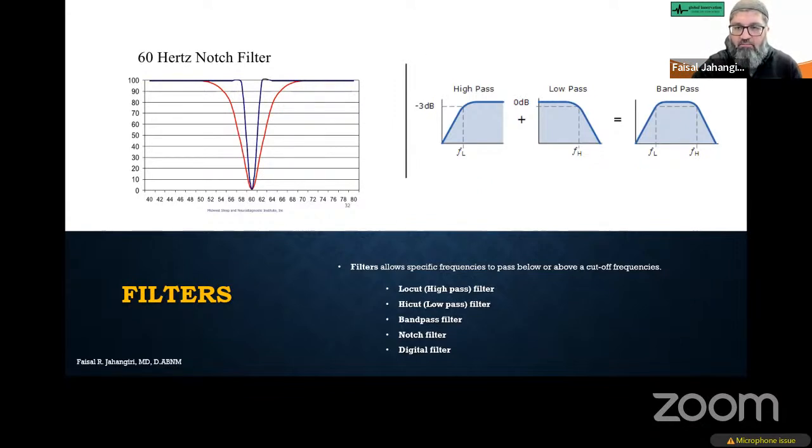The signals in the brain, the gray matter signals, are slow. And the white matter signals are faster. White matter is myelinated fibers, dendrites and axons, so they oscillate at a faster frequency. So we use a higher filter setting for subcortical and peripheral responses, 1500 hertz. But for cortical, we use lower filters, about 500 hertz.